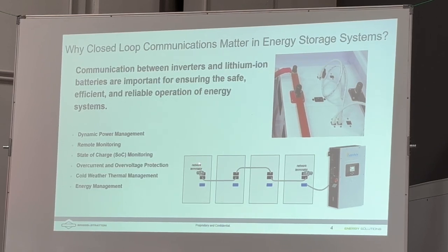So just to point out what closed loop communications look like - the batteries communicate through a protocol called CAN bus. CAN bus allows one battery to communicate with the next, and they call it a bus because the batteries are all connected in a line, with only the final one connected to the inverter. You want to make sure you don't have any open battery ports on those batteries.